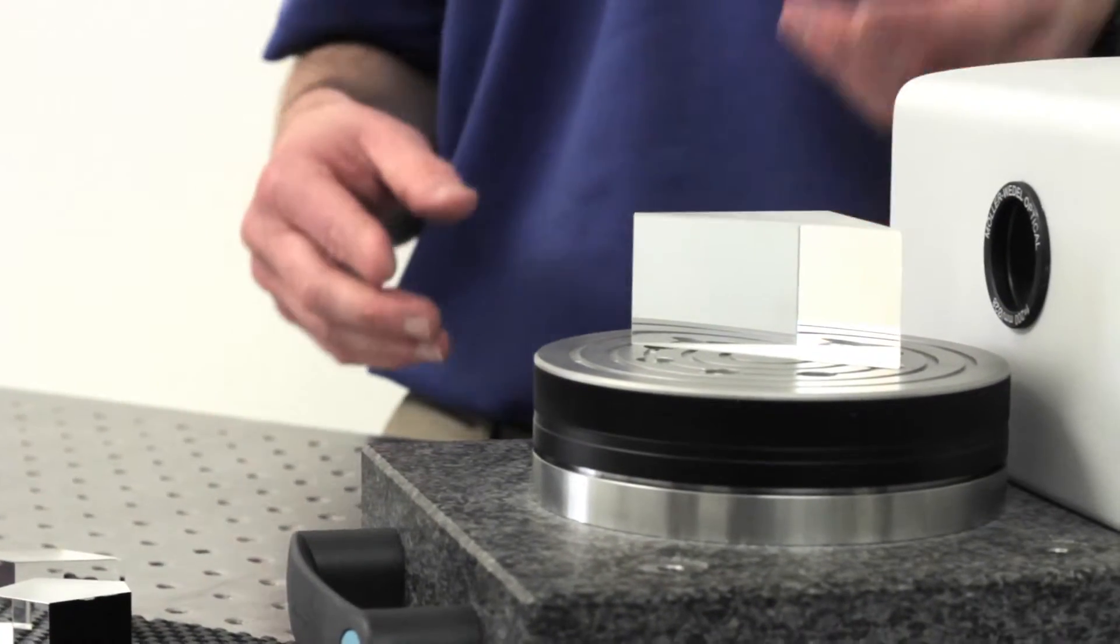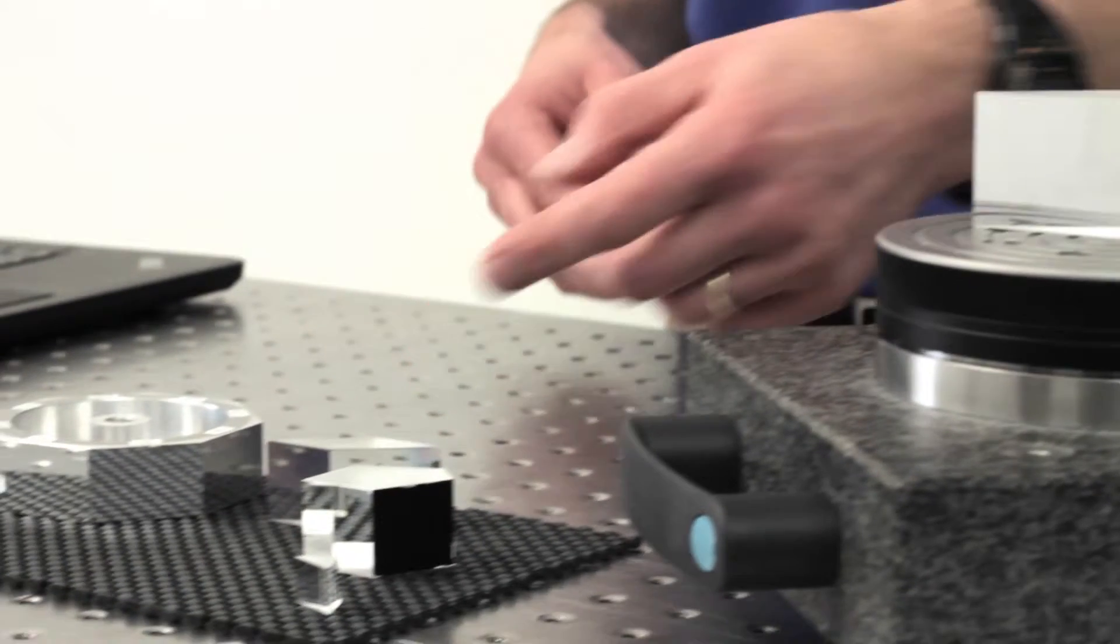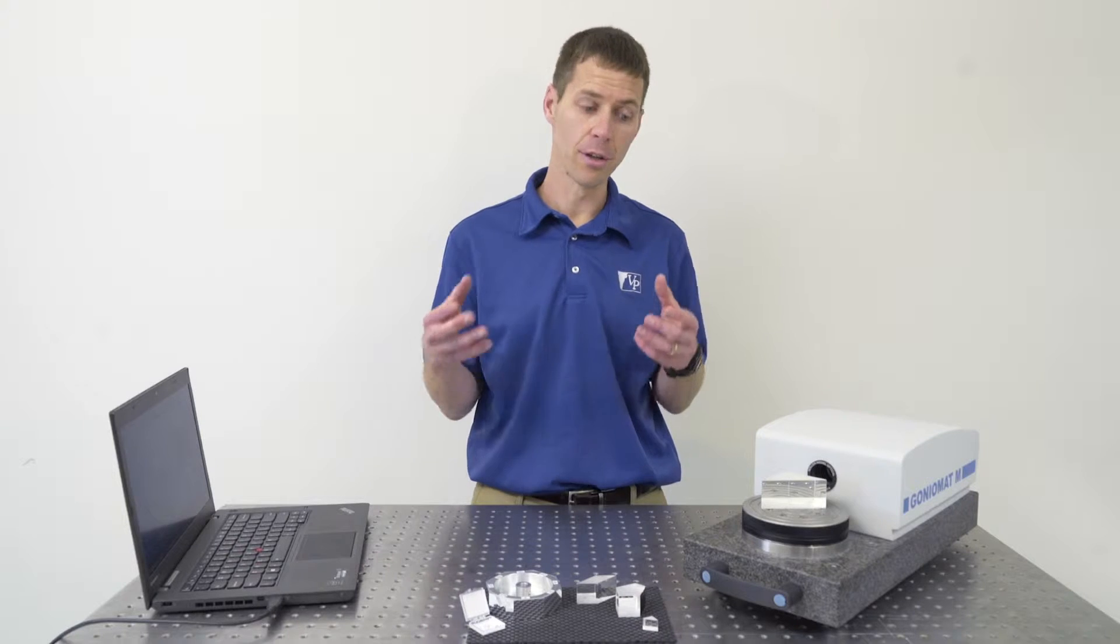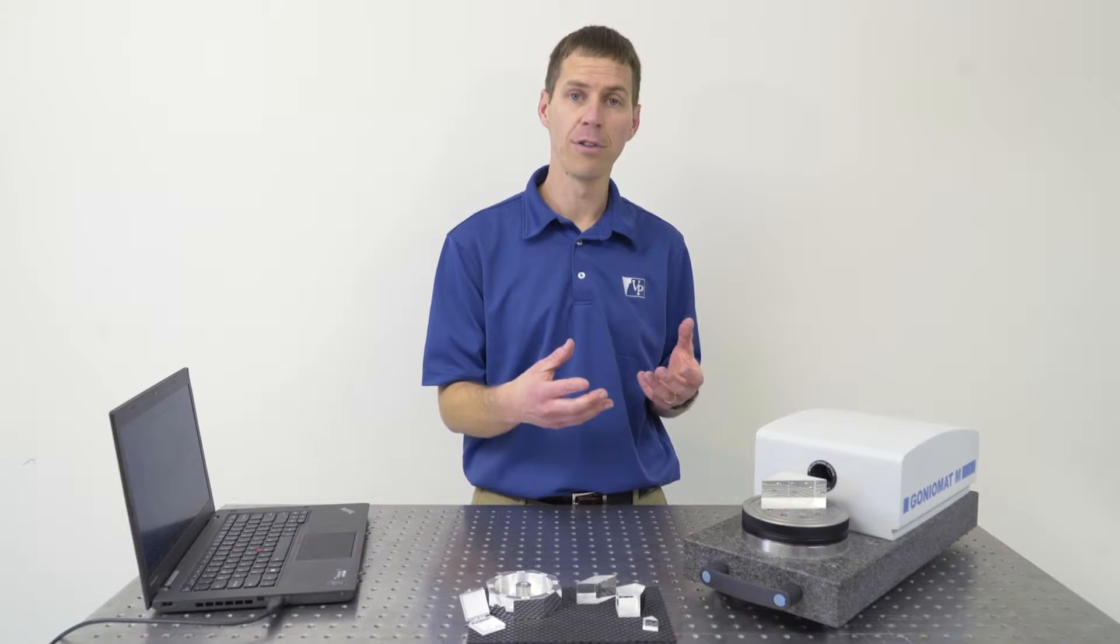You can also measure beam deviation, so if you're measuring a pentaprism or a mirror-based pentaprism or some other optical system, you can measure the beam deviation with very high accuracy by a number of different methods.